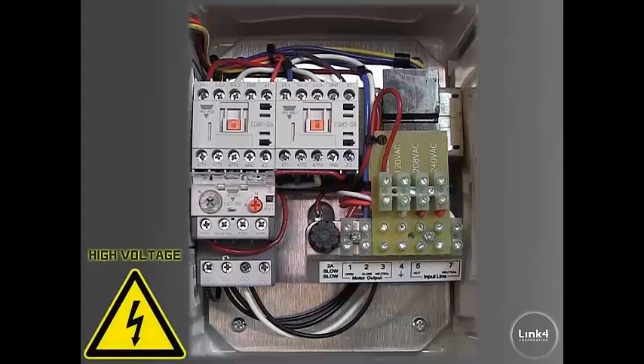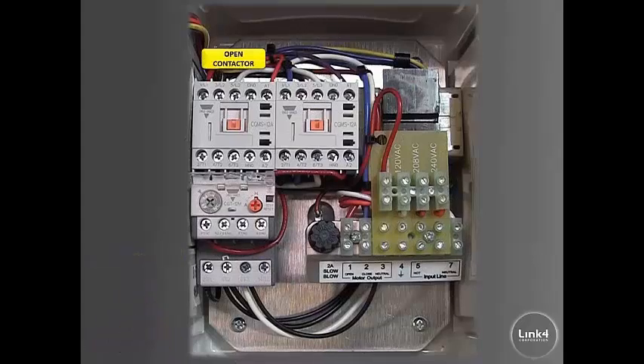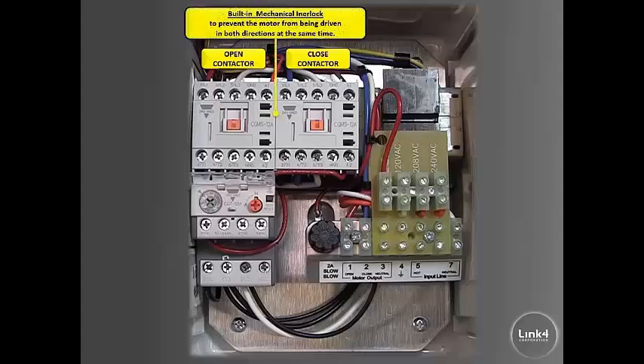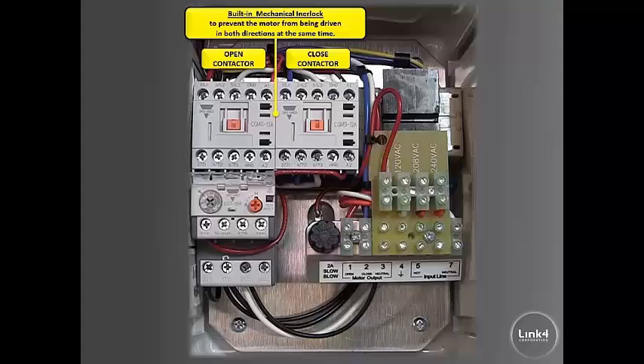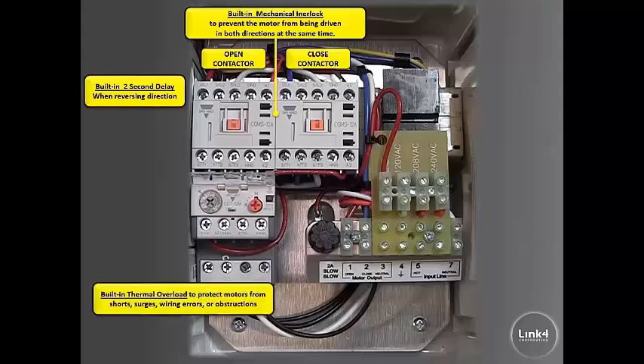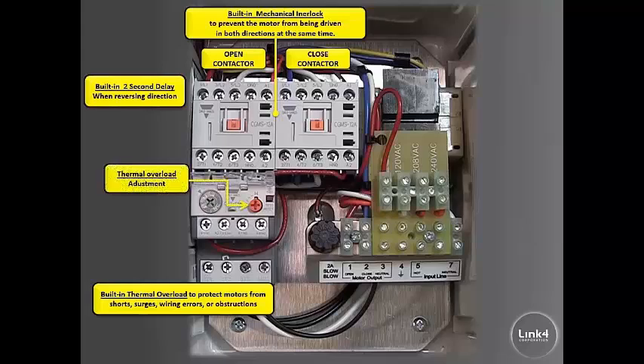On the high voltage side of the iDrive, you have an open and closed contactor with a built-in mechanical interlock to prevent the motor from being driven in both directions at the same time. You also have a built-in two second delay when reversing direction, a built-in thermal overload to protect motors from shorts, surges, wiring errors, or obstructions.